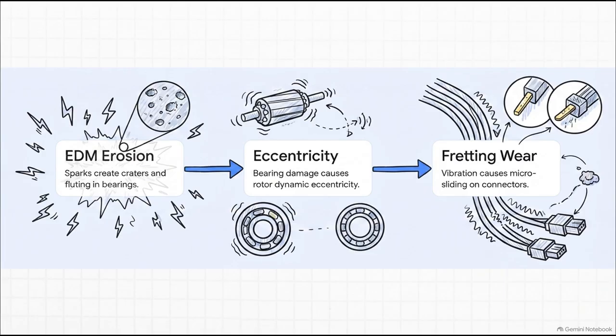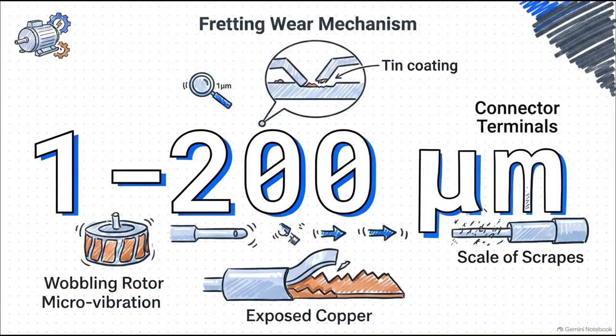Finally, step 3. All that violent, high-frequency vibration travels straight down the wires to the low-voltage connectors, kicking off something called fretting wear. To really picture fretting wear, you have to think on a microscopic scale, just 1 to 200 microns. Because of that intense vibration from the wobbling rotor, the male and female connector terminals start rubbing against each other in these rapid micromotions. We're talking movements as tiny as a single micron. But this relentless microscopic scraping is actually enough to completely strip the protective tin coatings right off the terminals, leaving the raw copper underneath totally exposed to the elements.